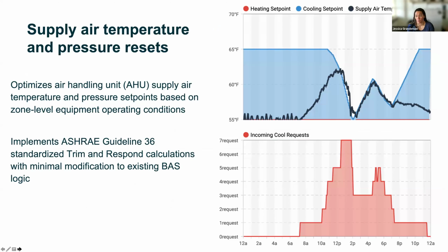We talked about demand flexible control. We've also implemented best practice all around, continuous supervisory from the analytics. In this case, this is AHU level supply air temperature and pressure reset strategies, implemented per our specs, Guideline 36 standard trim and respond. The team wanted to pursue this so they could minimally modify existing BAS logic, moving toward more of a push-based paradigm.